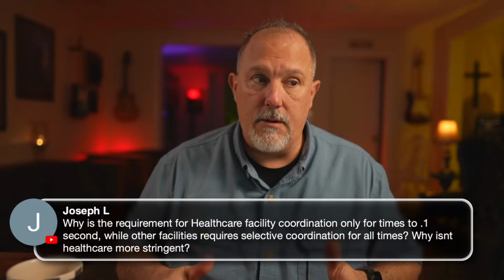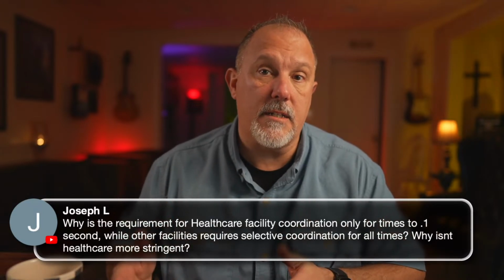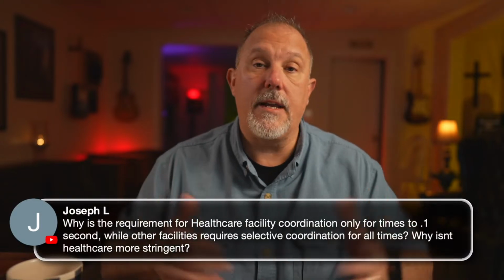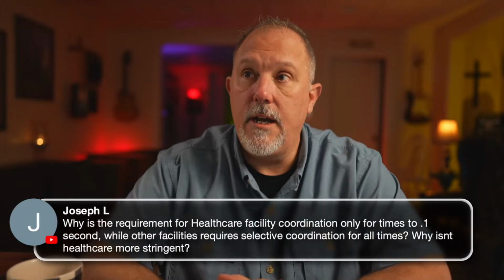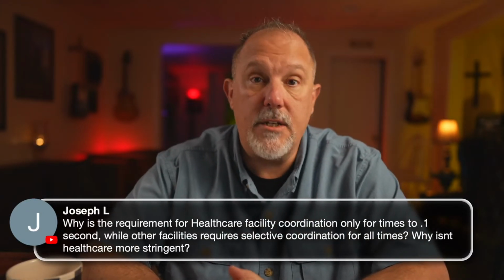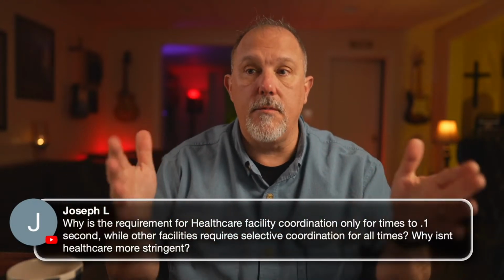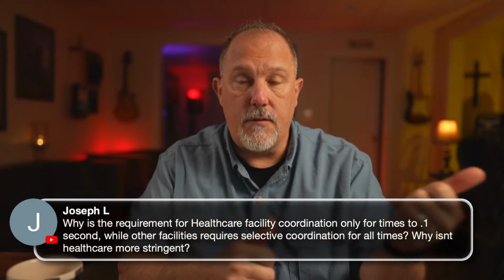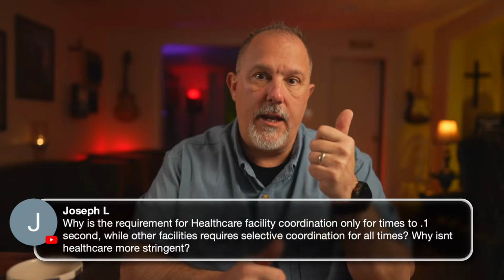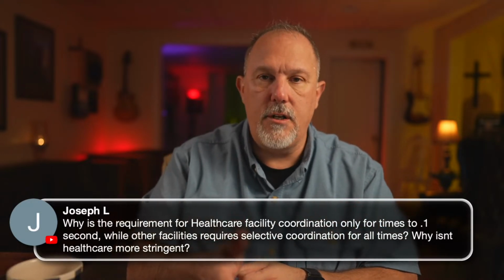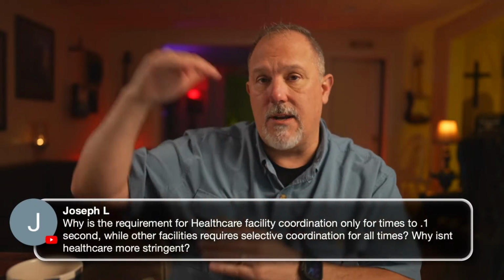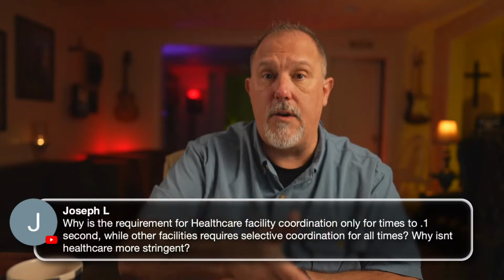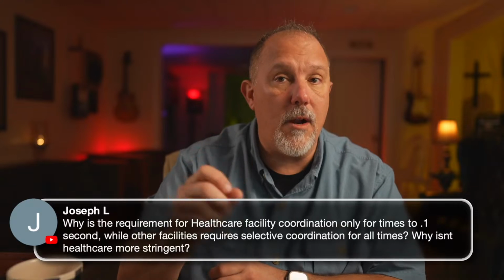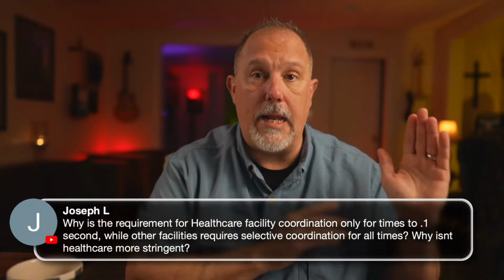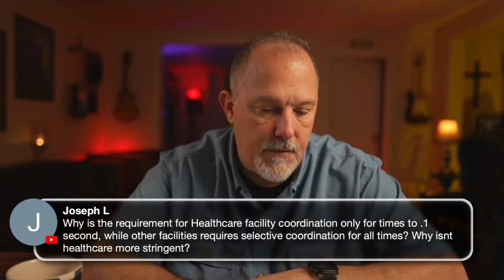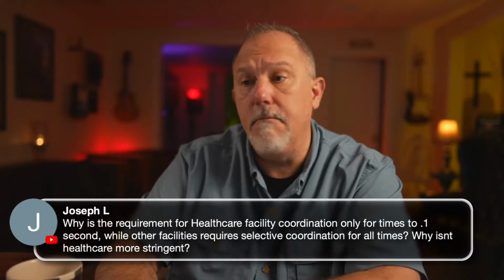so why is it there? The only thing I can tell you is cost. It adds more cost to the installation, and that's the only thing I can think of. I don't know of any other reason. I can't argue reliability because there's no requirement in the code for you to have 2 or 3 sources feeding a specific load. So if I think about lighting and everything else associated with it, if I lose one branch, I'm not talking about losing a source from a utility perspective, but if I have a fault in my power system and it takes out a feeder breaker, there's no requirement in the code for you to have multiple ways to power a load. So, Joseph, I don't know. I don't understand it, but hey, I don't necessarily agree with it.